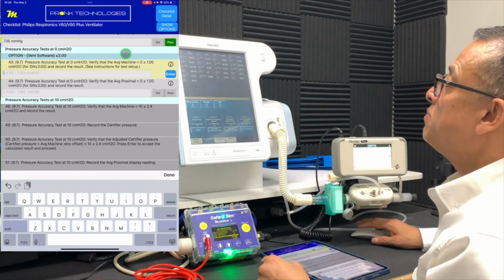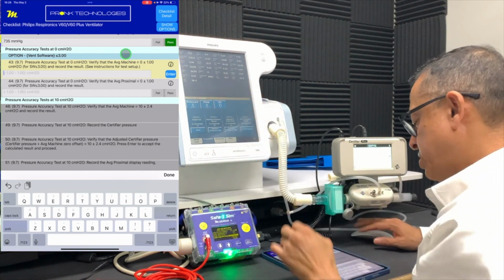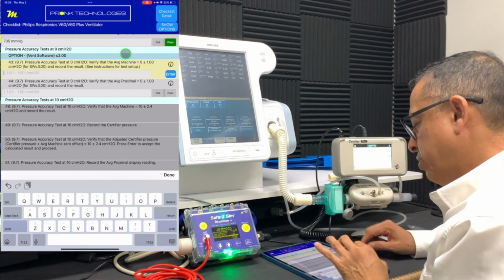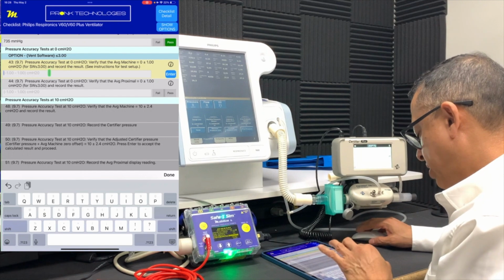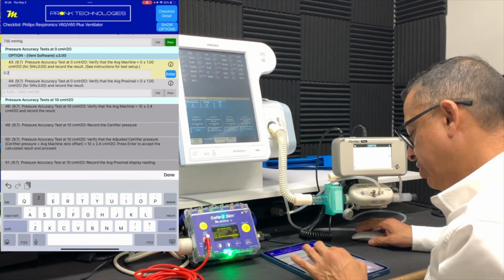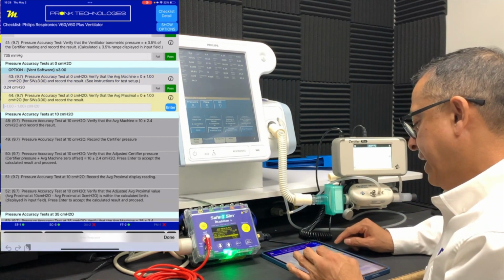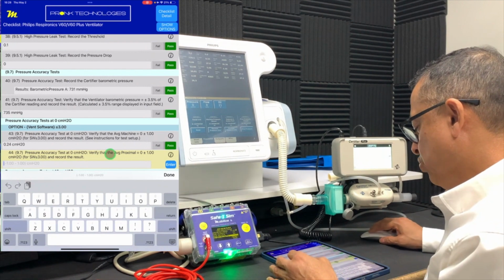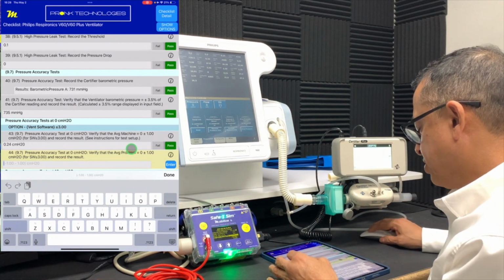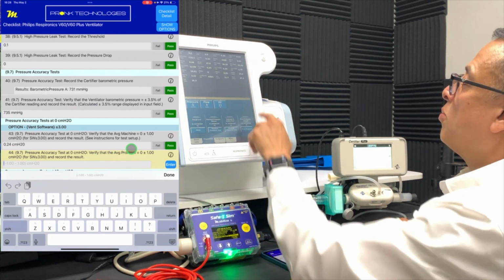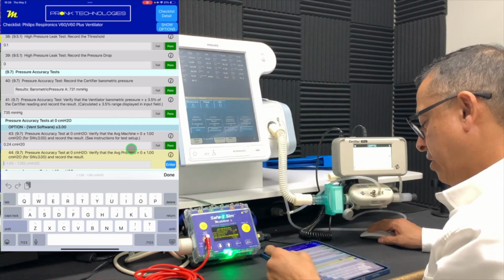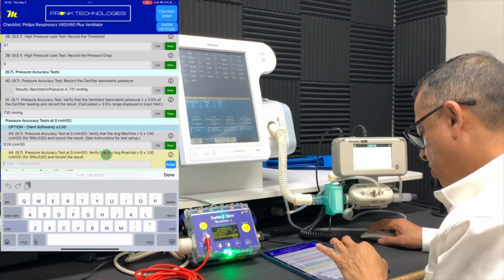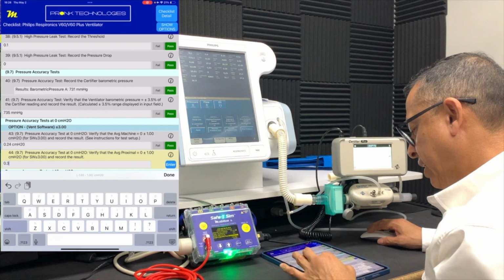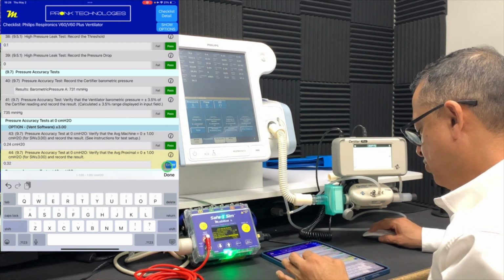So the average machine pressure at 0 is 0.24. You can see my ranges are already listed in here, so I know what's supposed to be the pass-fail range. I capture that and go on to the next one. This one is verifying the proximal pressure value. It needs to be 0 plus or minus 1 as well. And here we're at 0.32. So we've captured that as well.